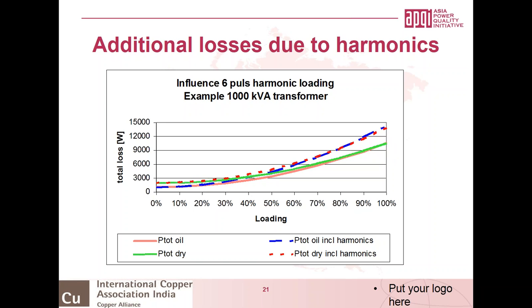If you look at it the other way, perhaps some people have asked me: in case I know I have a 100% loaded transformer, and I know that it has harmonics, why can't I take the amount of losses which I have at 100%, and looking back, work out what my maximum loading of the transformer could be in case I have harmonics, and then say, okay, I will go to just above 80% of loading.